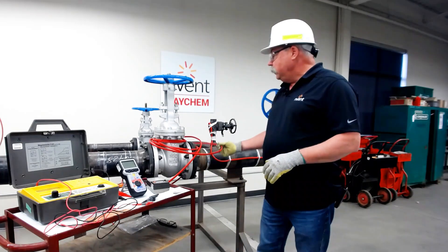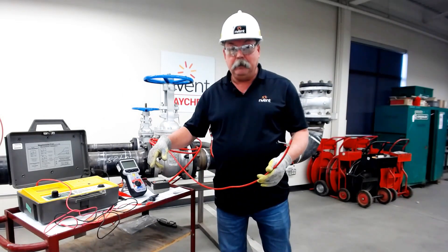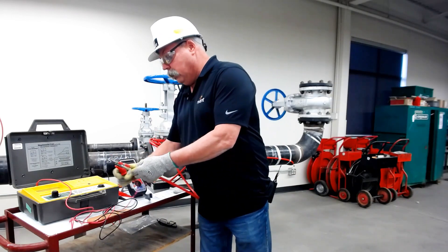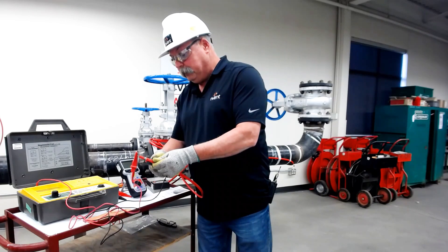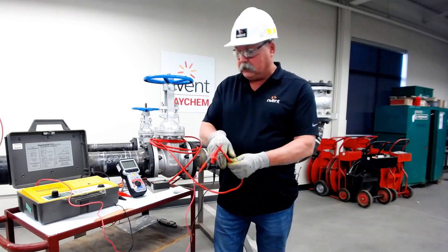When we do our testing, we want to make sure we're doing all three voltages for one minute each, and we want to make sure we're recording our values and writing them down. If you look in our manual you'll see that we require that — that's a Raychem spec.